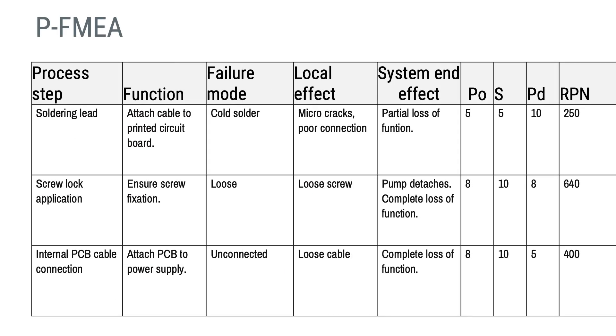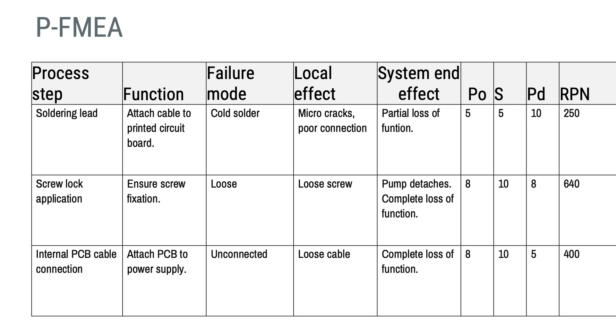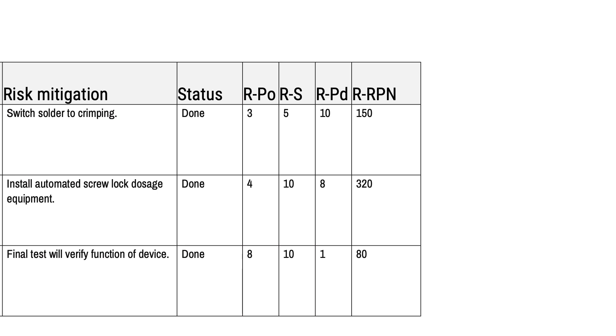Here is another example — in this case it is a process FMEA, or PFMEA. Instead of looking at how parts of the design could fail, we look at how the production process could fail. Please note the PD, which is an abbreviation of probability of detection or detectability. This is a measure of how easy it is to detect the failure and prevent it from being released and having an impact on the reliability of the product. The more likely the failure is to be detected, the lower the PD score, meaning the risk would receive lower priority on the RPN scale. Sometimes we can implement really efficient in-process controls or final tests that will prevent a future user from experiencing the consequence of our process failures. This brings down the residual PD score, lowering the residual RPN number.